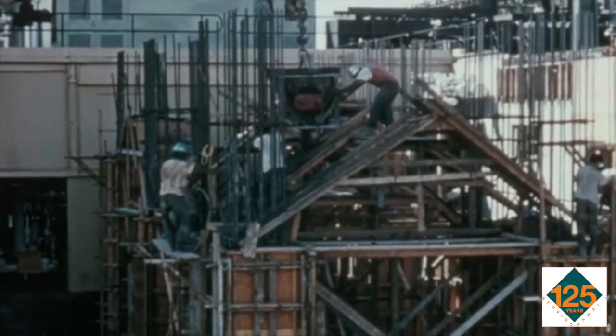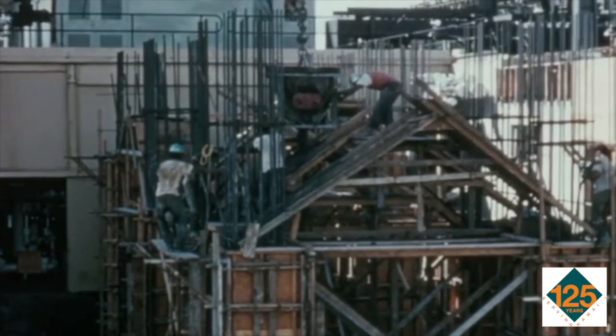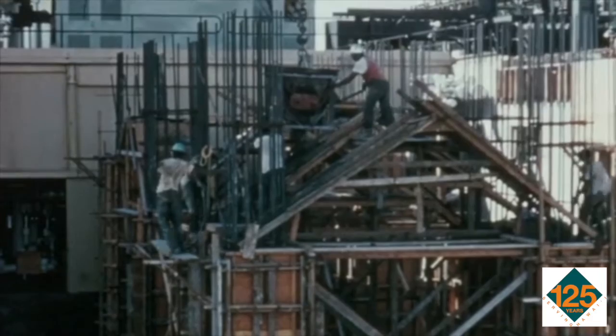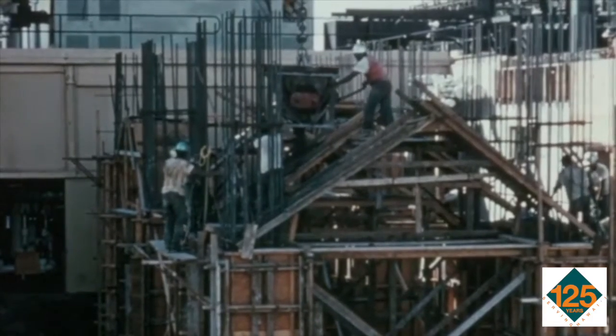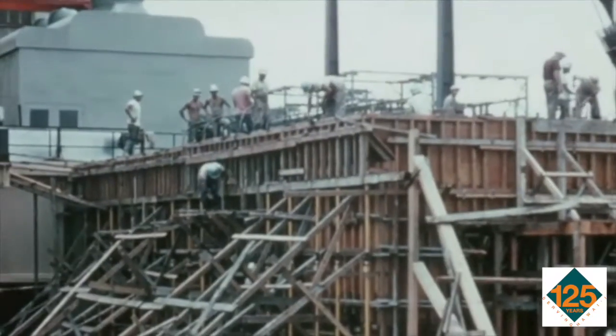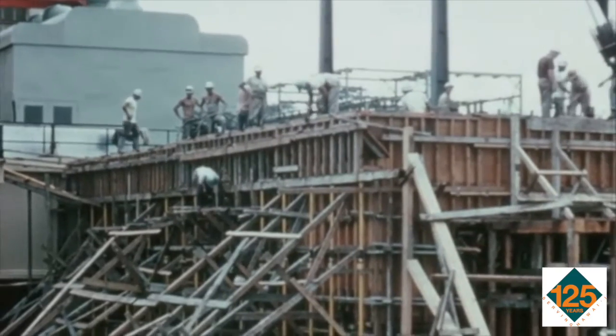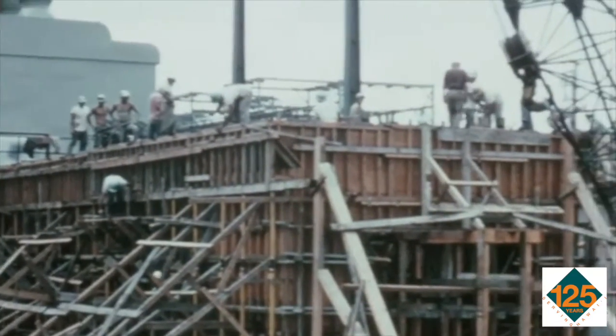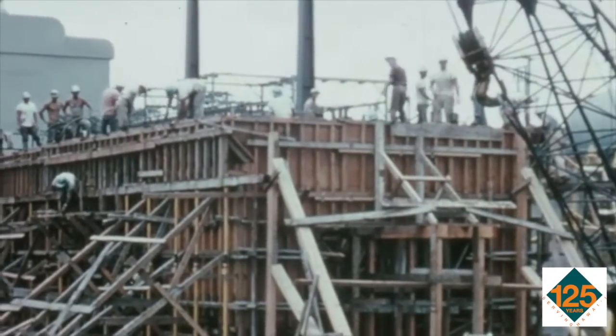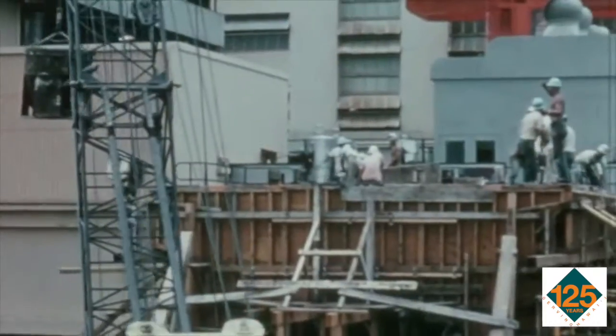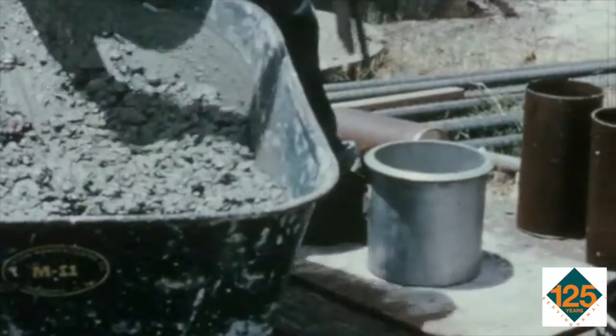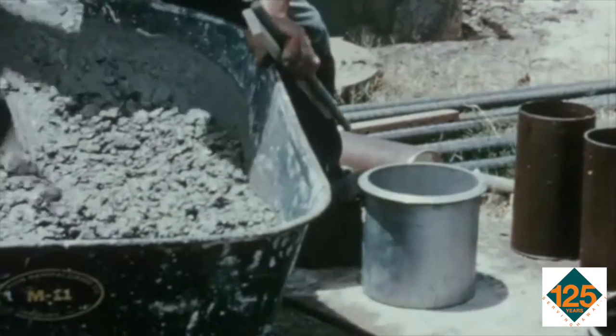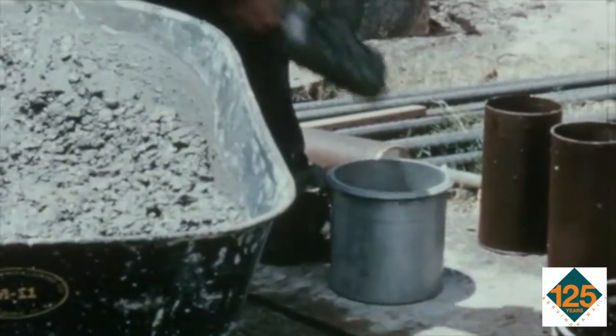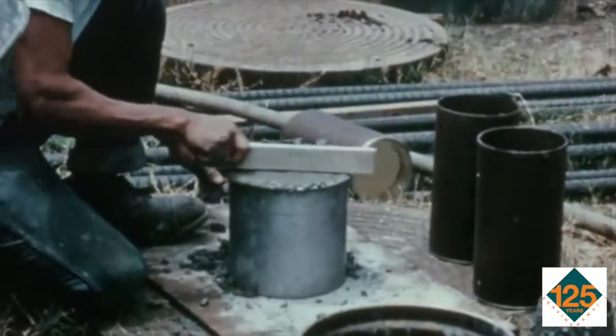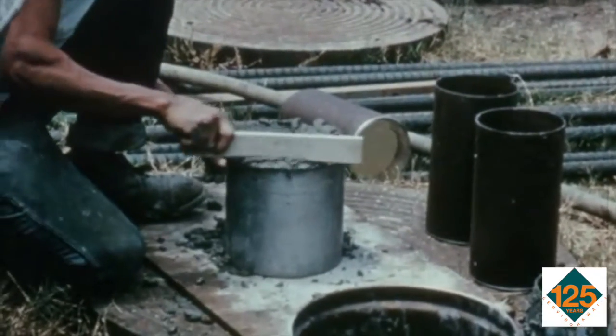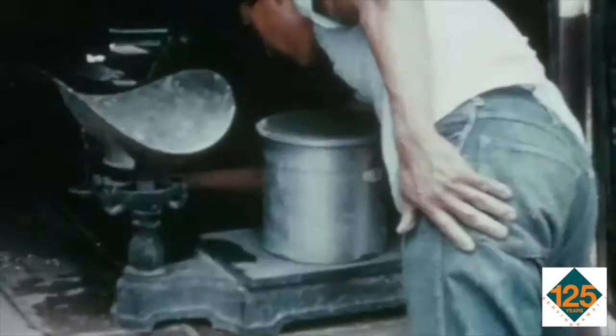The concrete foundations beneath the turbine generator unit must be extremely strong and heavy to hold the machines in place while they are driven by the steam at a speed of 3,600 revolutions per minute. Daily tests of the concrete were made to ensure the required strength when cured. Samples of concrete were put into cylinders and crushed by large presses to test the strength of the concrete.